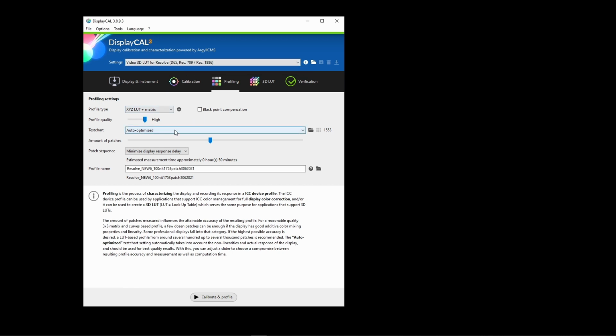The test chart here, auto-optimized, that's a good selection, and you can then choose the patch range that you want. So the more patches you have, the higher the quality of the profile is going to be. It comes up with 1553 standard, but it's not a bad idea sometimes to do 17-point profiles. But for this little exercise, we're going to do just a small one of 175.